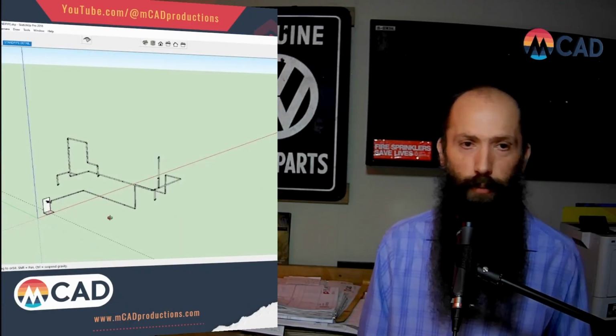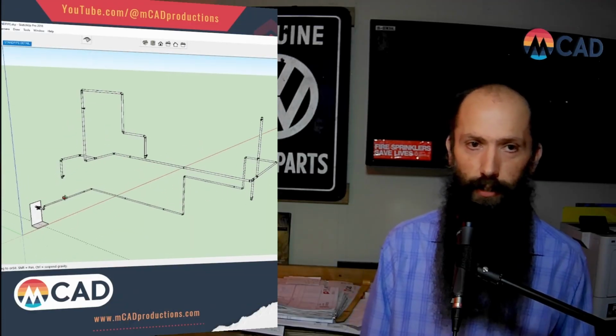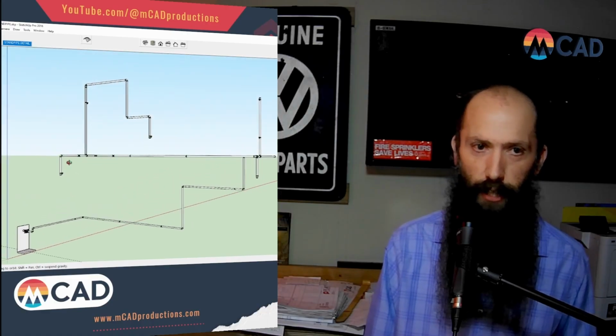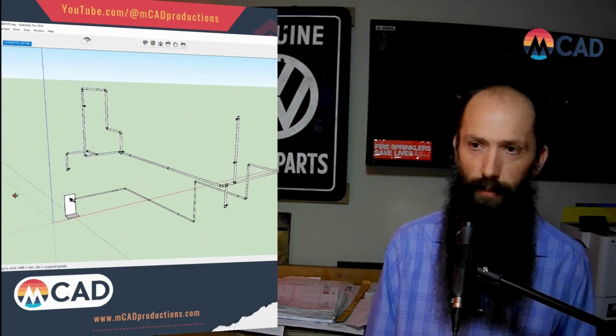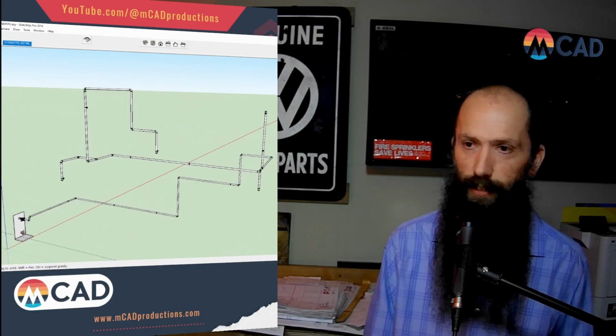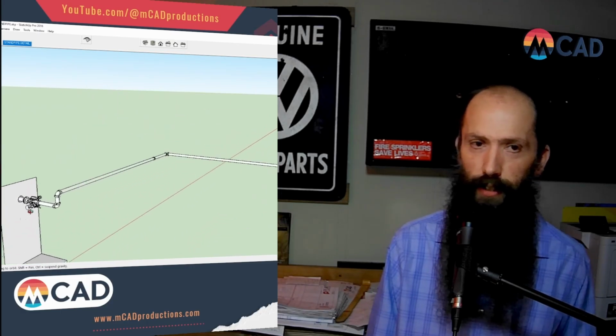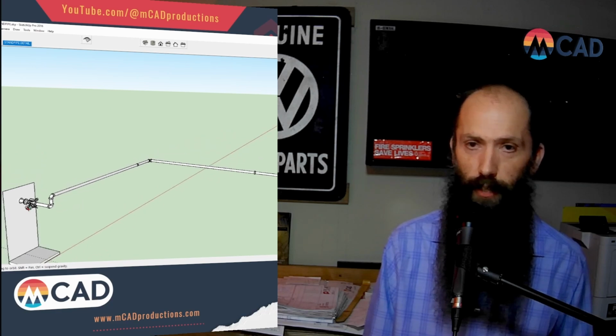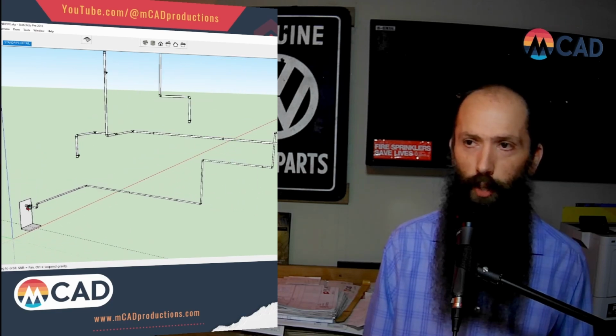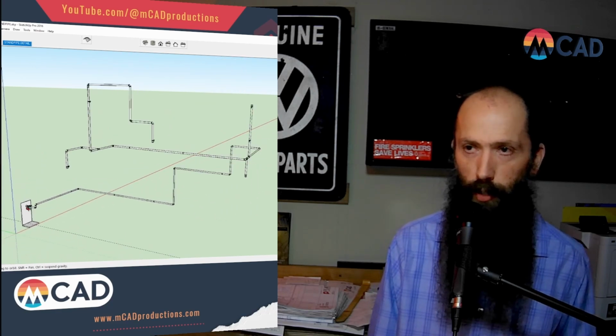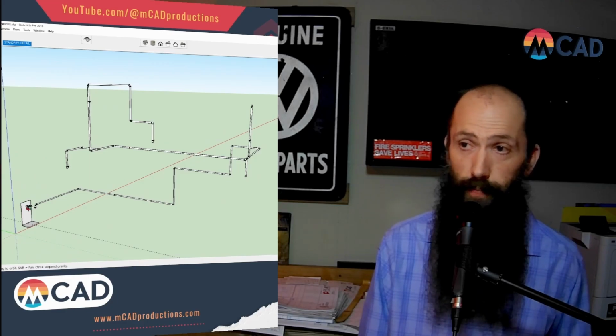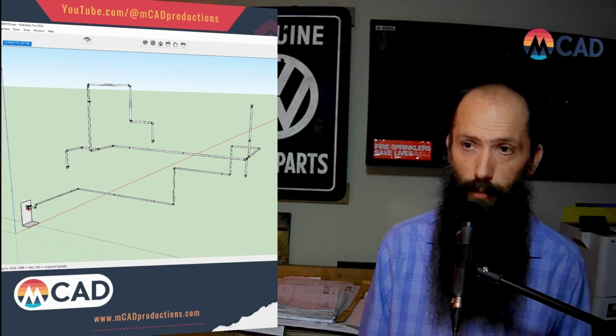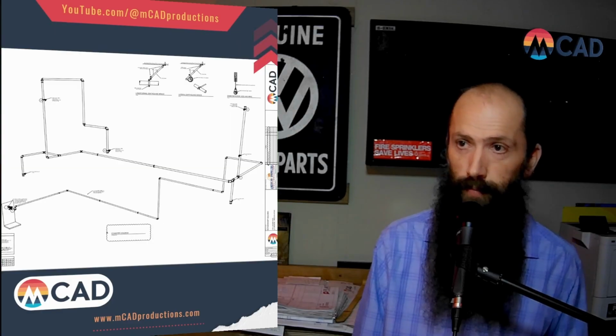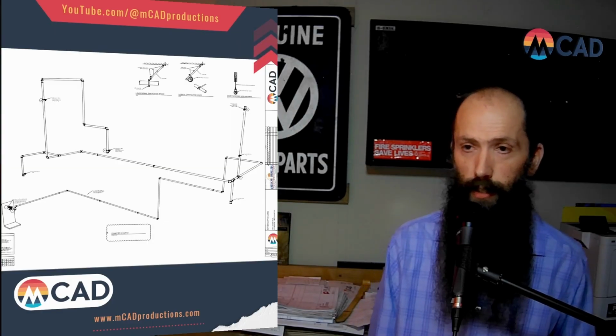And they ended up having to use a 4-inch and doing a standpipe. So this is actually that same building. It's kind of a convoluted standpipe because the building was never designed for this. Well, we were able to make it work. And this is the 4-inch pipe that they had to bring in to feed that. We have a hose connection on both stairways at every level. You could kind of tell from this possibly that the stairway to the left is split into 2 stairwells. And this is the final detail that we were able to make from it.